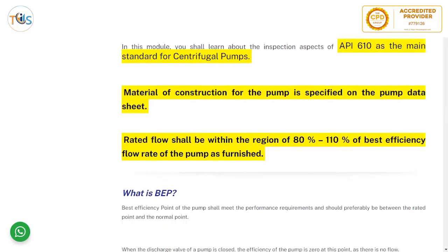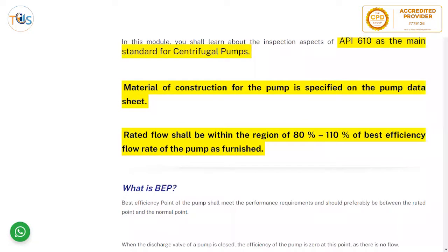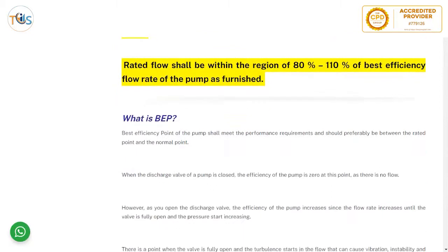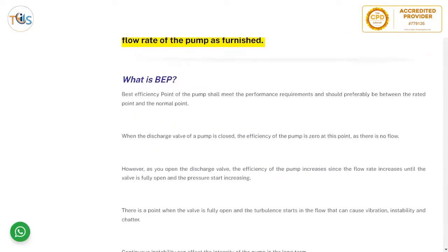The rated flow shall be between 80 percent and 110 percent of the best efficiency flow rate of the pump — that is the normal operating range. The best efficiency point of the pump shall meet the performance requirement and should preferably be between the rated point and the normal point.